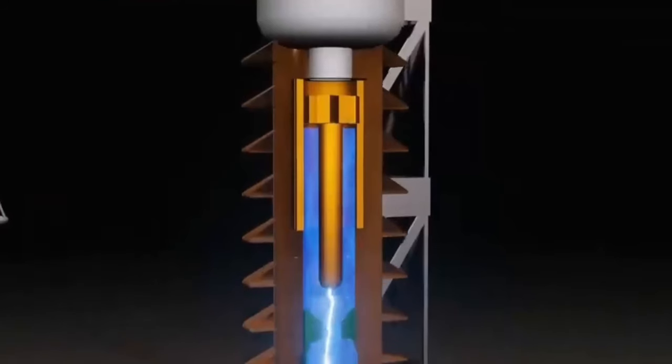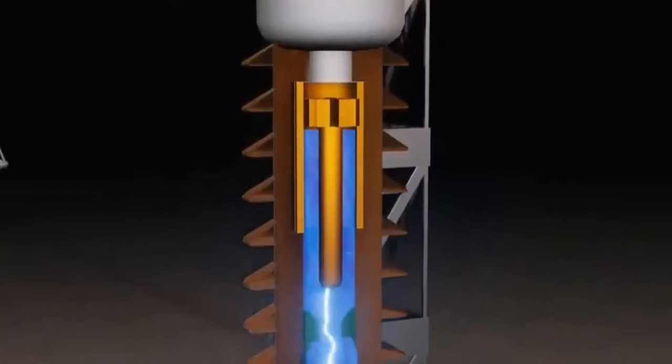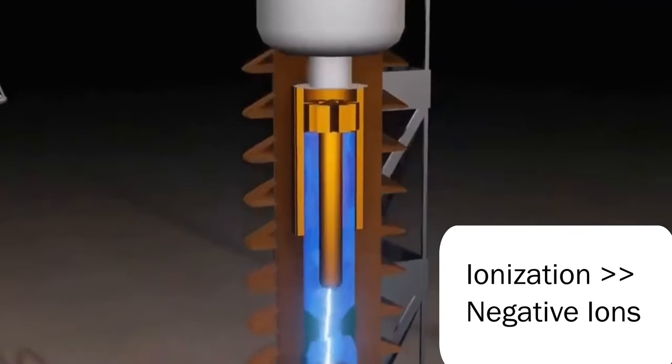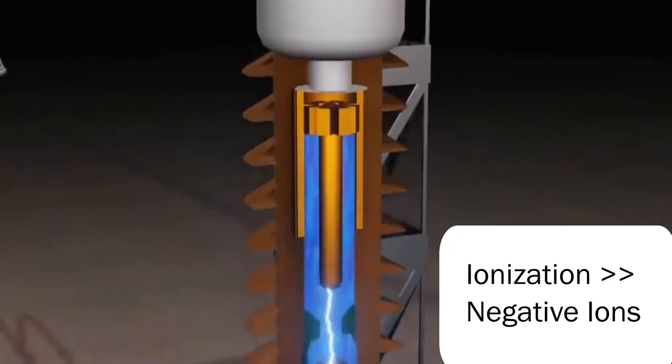Sulfur hexafluoride is able to extinguish the arc because high temperatures cause it to ionize into negative ions, which prevent free electrons from moving and thus eliminate the arc.